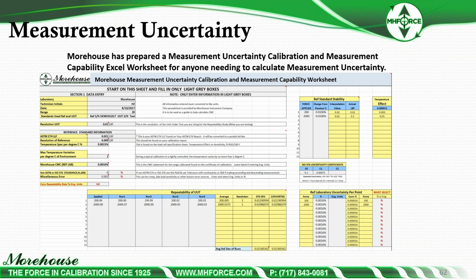But getting to our guide, so you've got a calibration in accordance with E74 or 376 or something else. We have an uncertainty guidance document that I can share with anybody. But if you've got it in accordance with ISO 376, you enter your equation here. Here you would select ISO 376. Right here it still says ASTM E74 LLF.